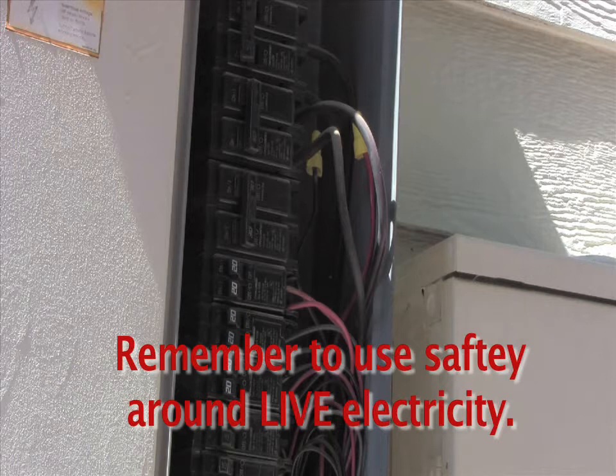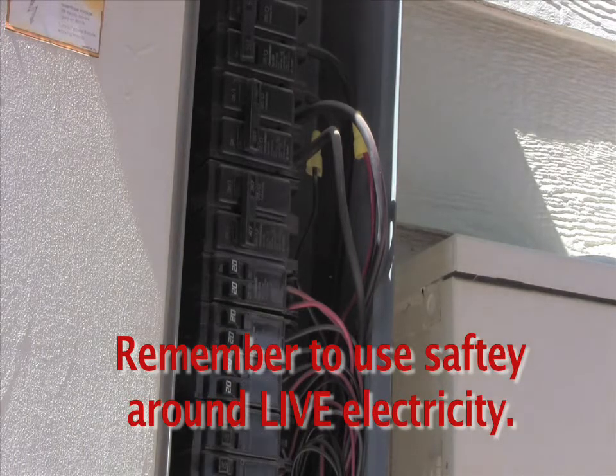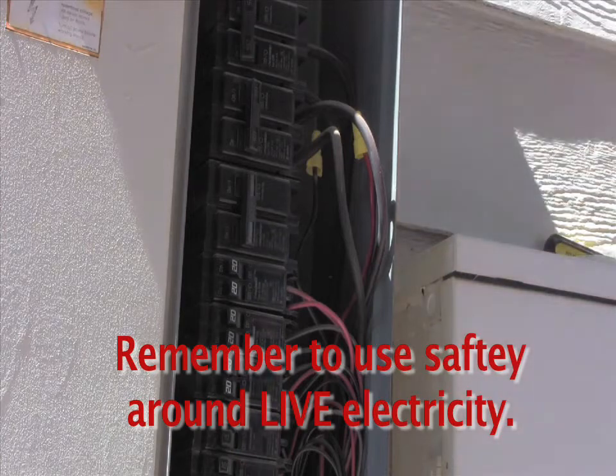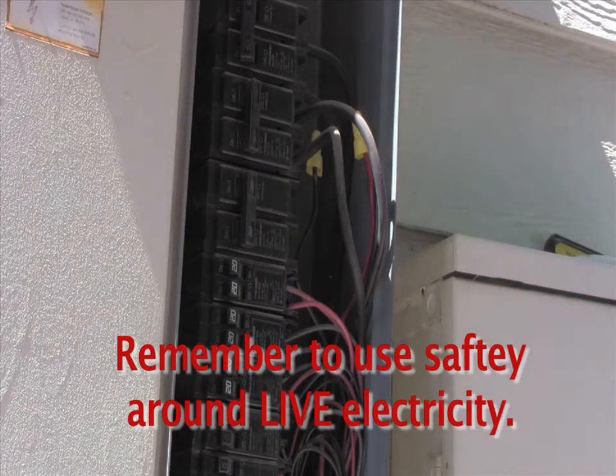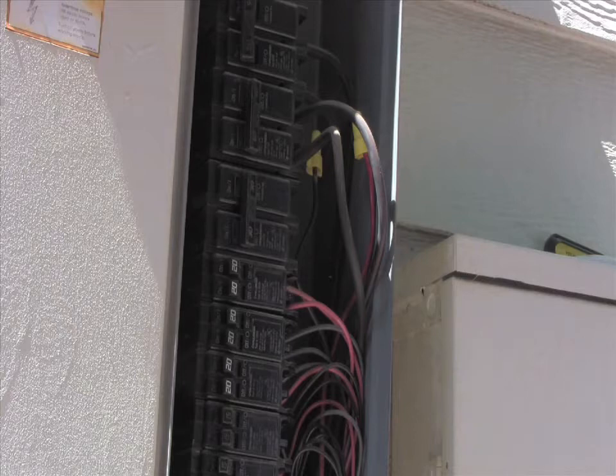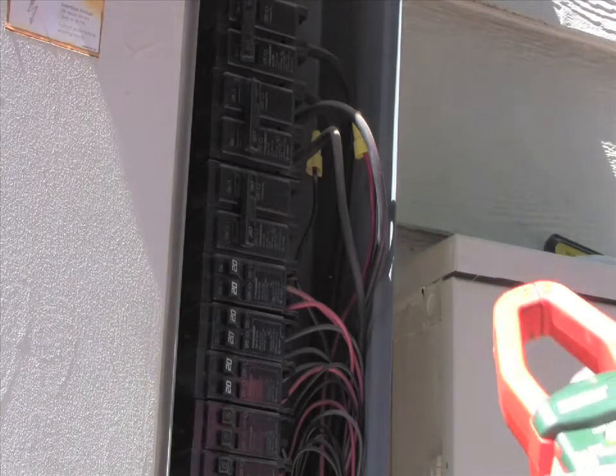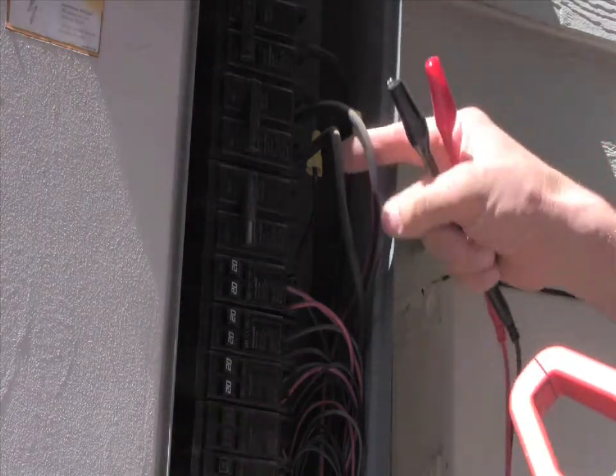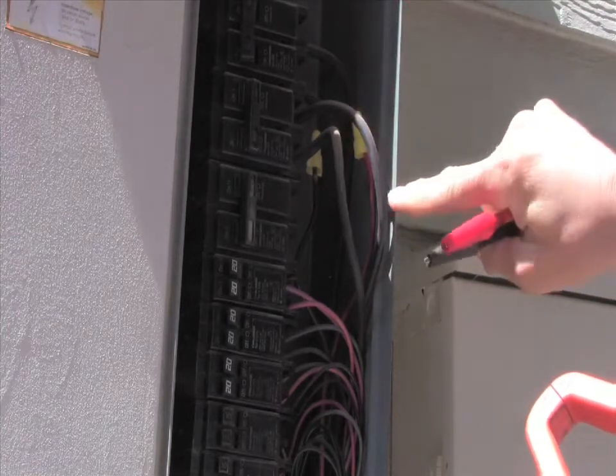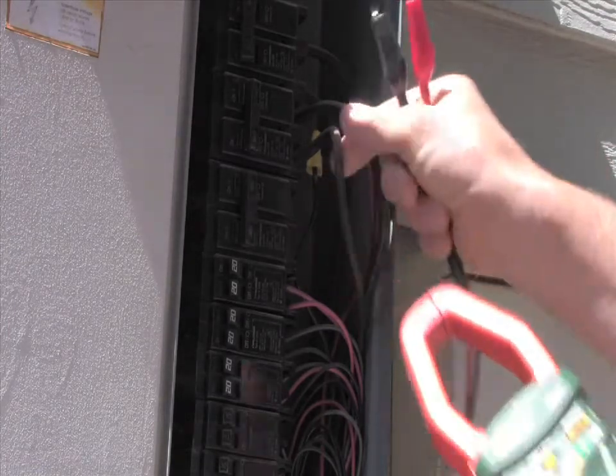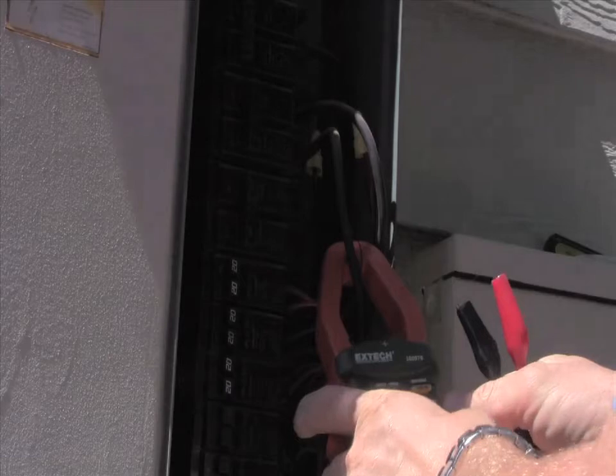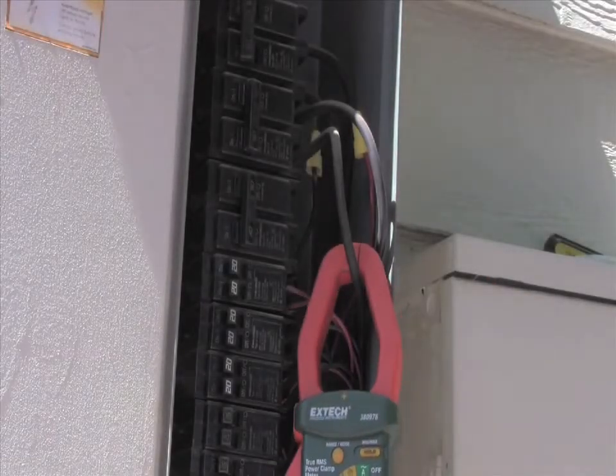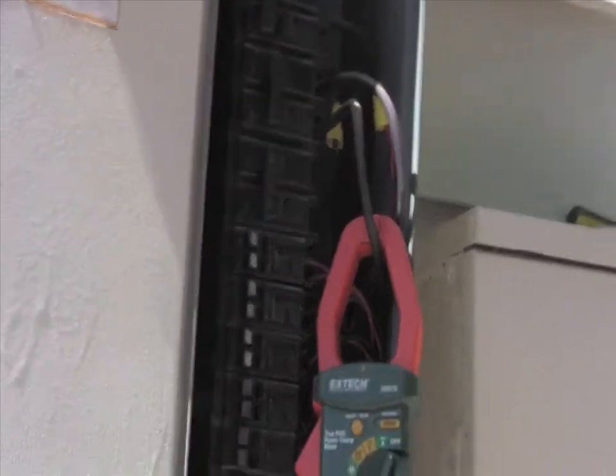So we've identified the two leads that we're going to use to measure. And the first thing we do is we take our trusty dusty meter here. We're going to clamp on this leg here. This one has a red line on it. It may be faint to see. This one obviously has no red line, so this is going to be leg 1, and it's black. So the next thing we're going to do is we're going to come down here. Let's see if I can show it.